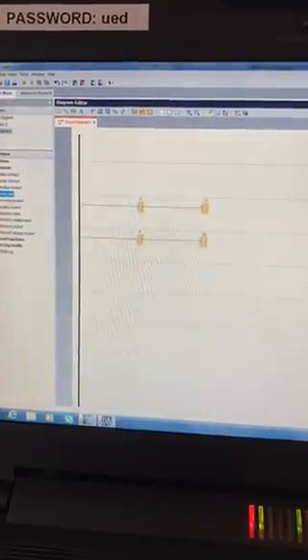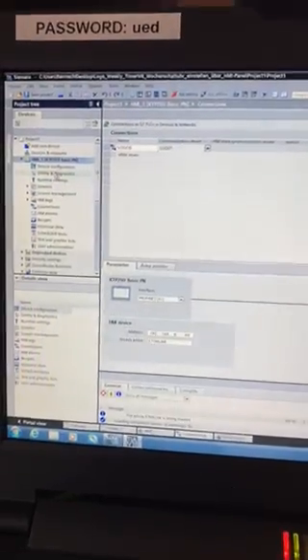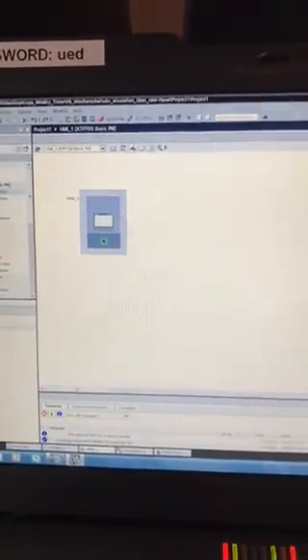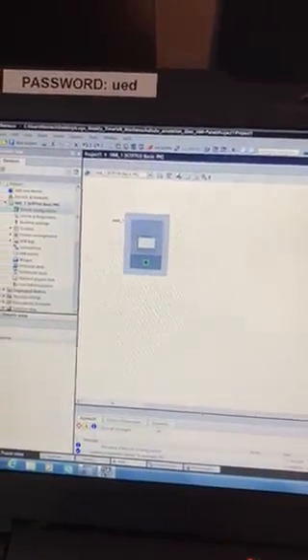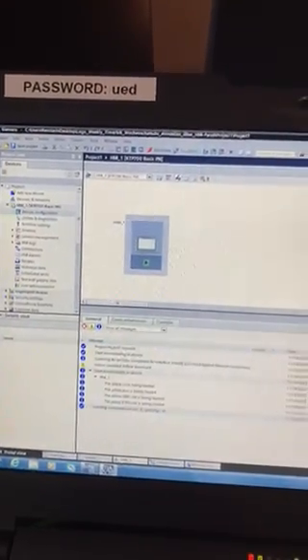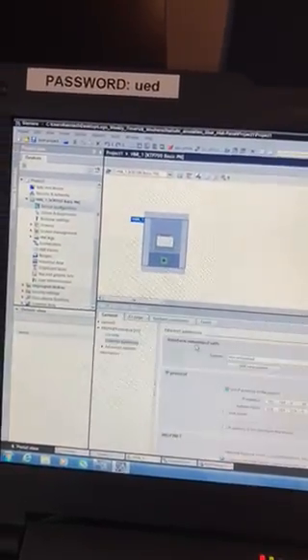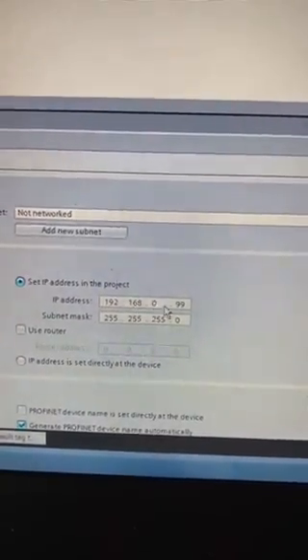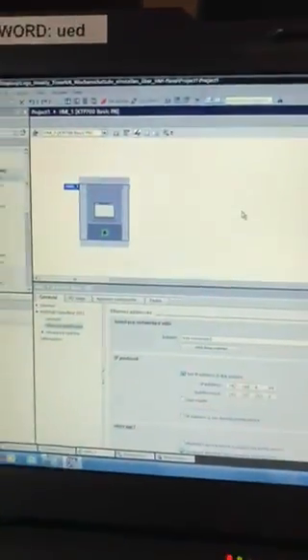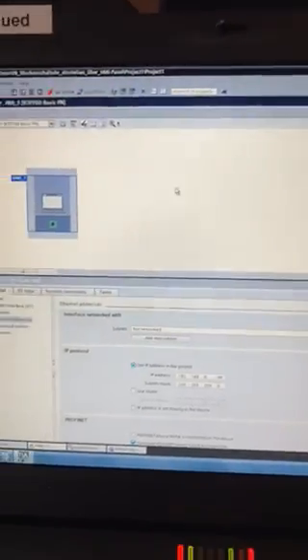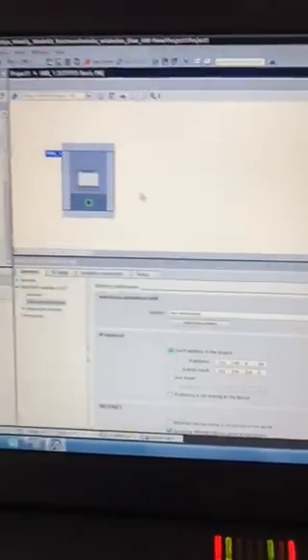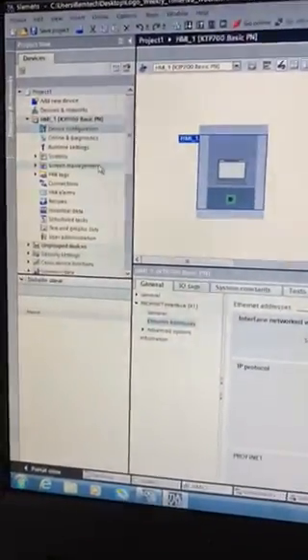From within TIA, the first thing I did was in my device configuration I set my IP address in my properties. There's my IP address 192.168.0.99, and once I set that IP address I sent it down to my HMI so it had a new IP address. You can do it from within the HMI settings if you wish, but I've done it through TIA.